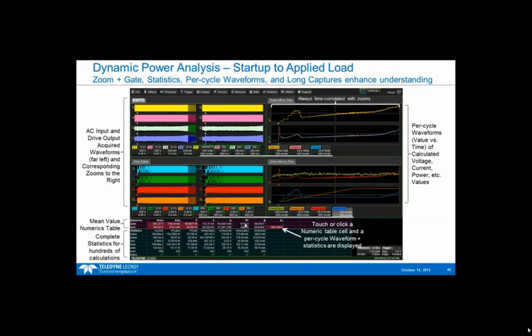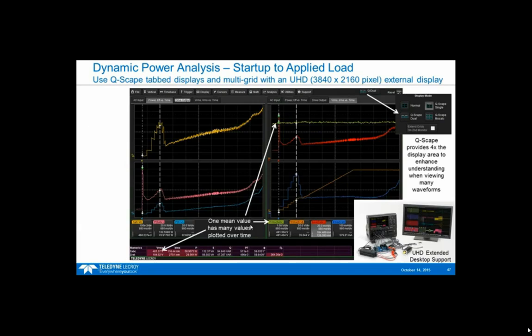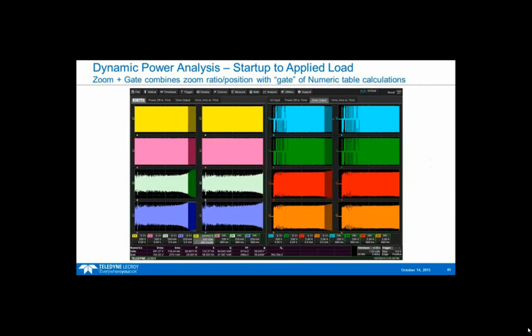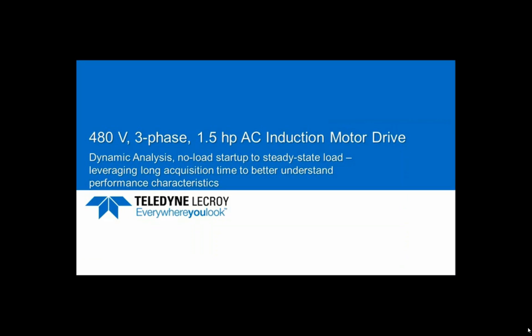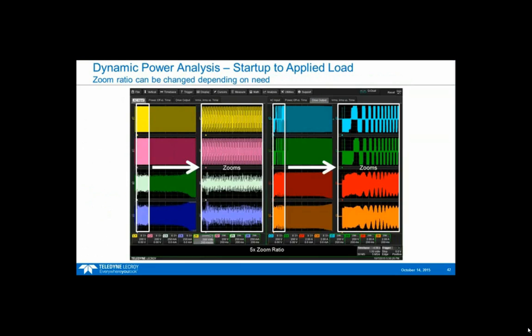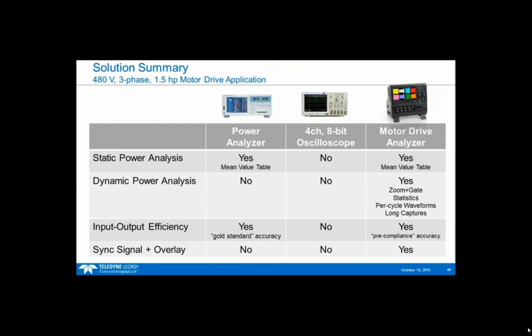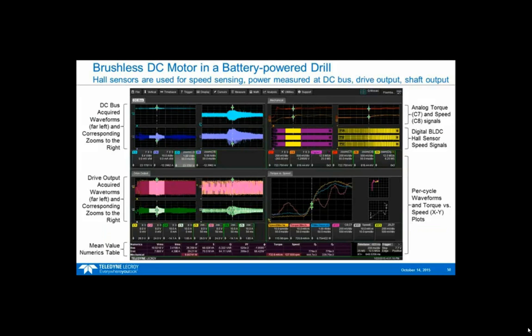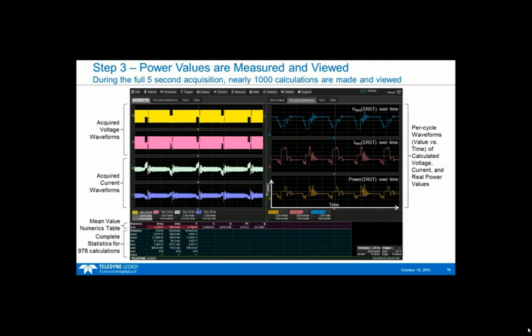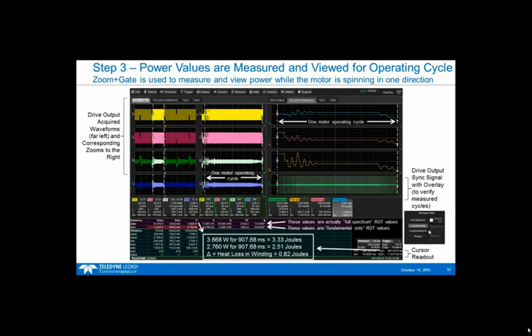This value represents whatever I've set with the harmonic filter. Within the drive output setup tab, there's a place to set the harmonic filter, and this is what it looks like within that tab. I can set it to the fundamental only, which will harmonically and digitally filter and just look at the fundamental waveform for calculation of power factor.